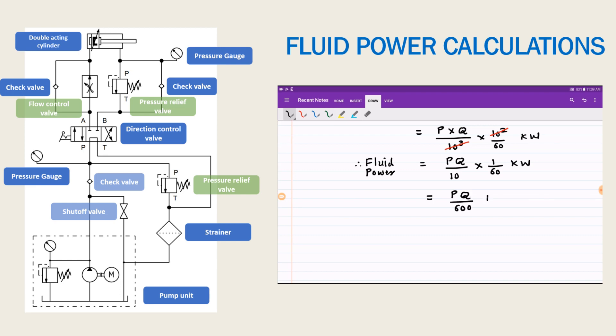We can directly use this formula for the calculation of fluid power when pressure is expressed in bar and q is given in liters per minute: fluid power equals p times q divided by 600 kilowatt.